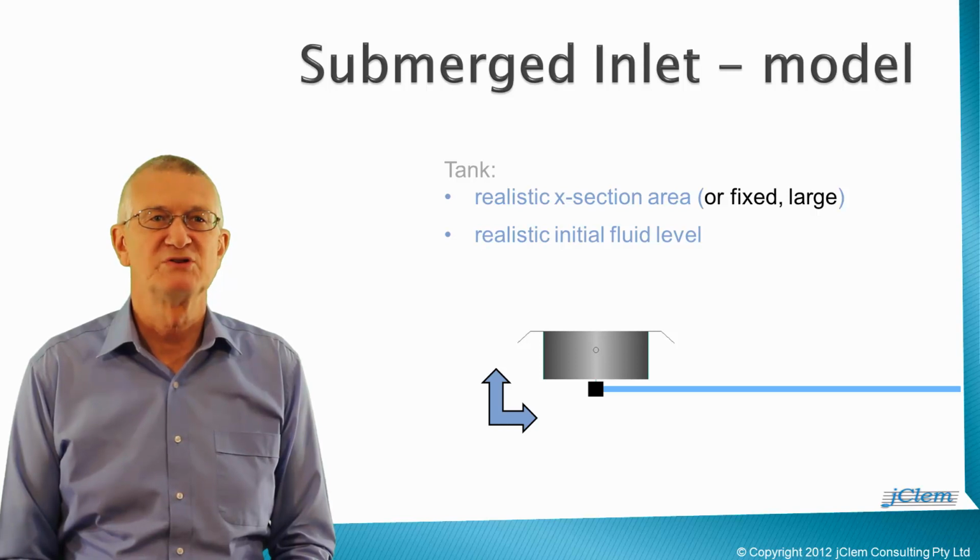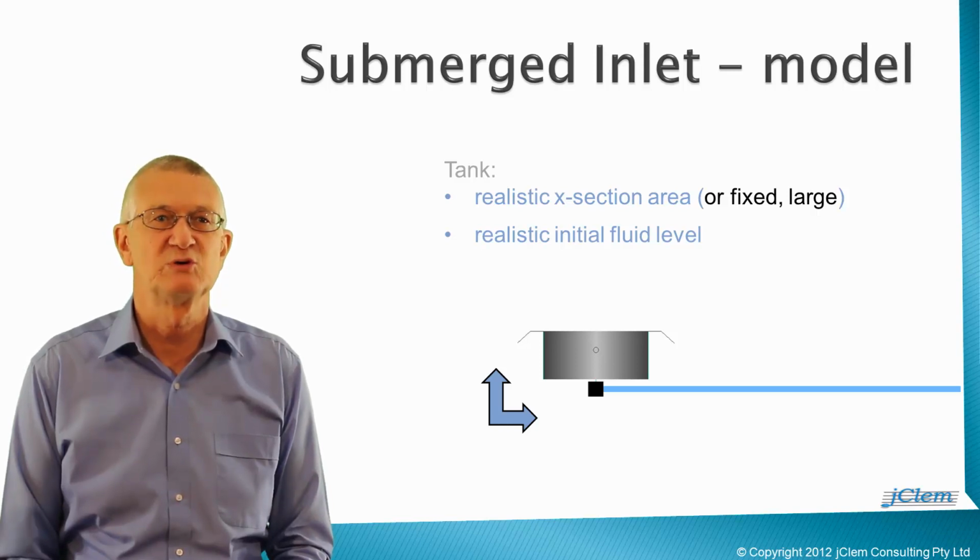This modelling approach assumes that fluid can freely flow into and back out from the storage. The actual ability for reverse flow to occur during transient events may not exist in some terminal discharge arrangements. It is all too convenient to just drop a reservoir onto the receiving end of a pumping pipeline model, particularly when the project team's objective is to deliver the pumping station and pipeline, not an existing sewer manhole or an existing water tank.